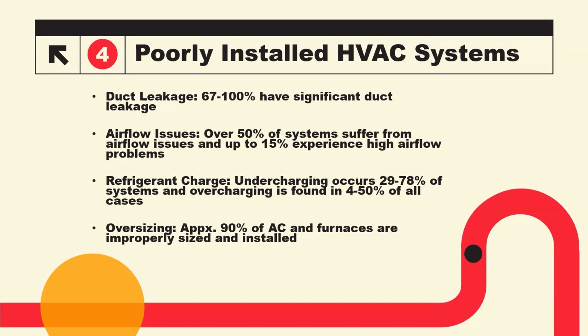Refrigerant undercharging occurs in about 30 to 78% of the systems. Overcharging is usually found anywhere from 4 to 50% of all cases. And then approximately 90% of the AC units and furnaces are improperly sized and installed.